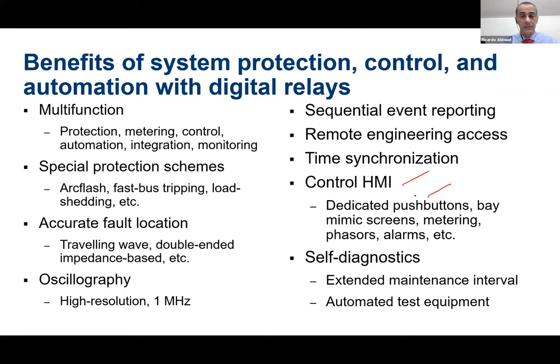So they have dedicated push buttons to control, open, and close the breaker, and open and close disconnectors. We can have some relays with a large, color touch screen display, so we can have the bay mimic screens. We have metering included in the relay. Some people can say, hey, but this relay is connected to a protection class CT. But remember, the protection class CT has a good accuracy around the nominal current. The 10% error that some people say the protection CT has is for 20 times the nominal current and when we have the nominal burden connected. When you're using the metering function in the relay, it's not 20 times the nominal current. It's close to the nominal current. The accuracy will be much better, like 2%, 1%.